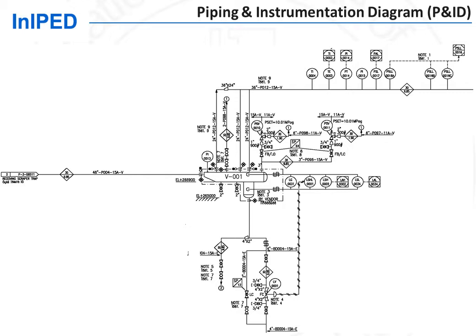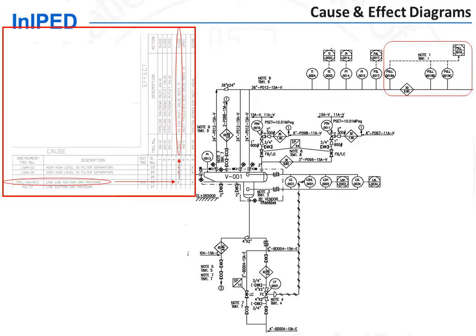Process discipline is indeed responsible to design the process and emergency shutdown systems. These systems include sensors as well as final elements which include shutdown valves. This system is designed to bring the process to a safe condition upon deviation of process parameters outside their normal operating range. The logic of operation of the process and emergency shutdown system is shown on the cause and effect diagrams.